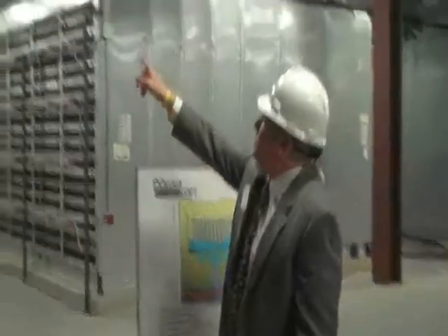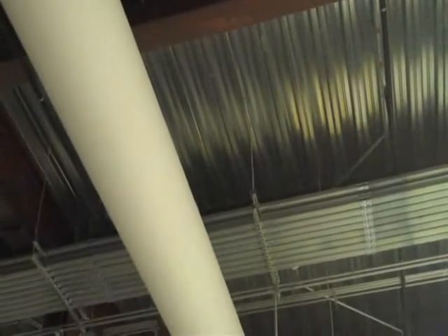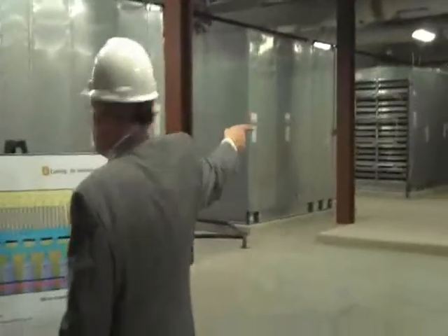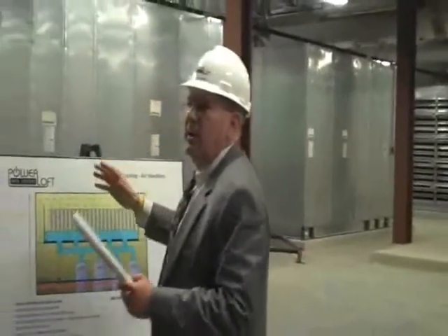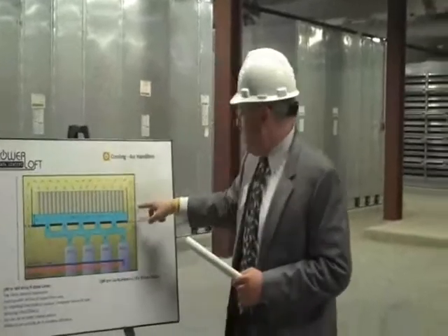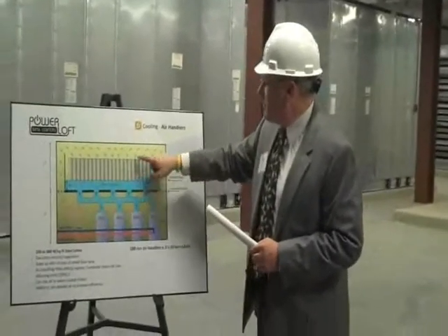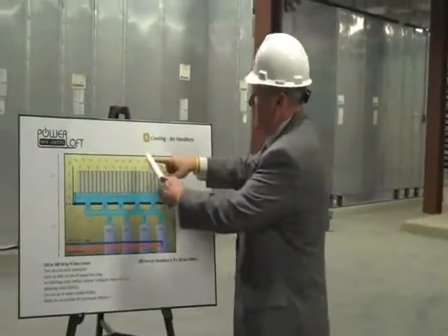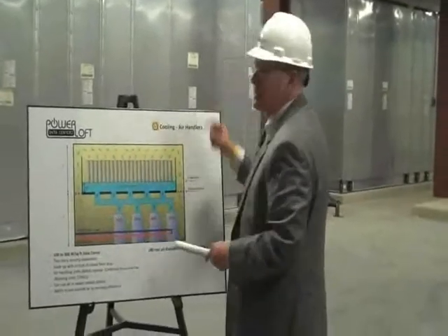Then, if you look at the jacketed ductwork right here above this pipe, it goes up again. That's pushing up to the raised floor, the underside. If you look right above you here, that's what's pushing up through. There's one of the louvers, since this bay hasn't been filled out yet. But if you were to walk to each end of the room here and look up, the last 12 feet beyond those diagonal shear braces for the structure is open to the second floor. And that hot air goes up through the racks, cools, comes back down, and goes back into these units.